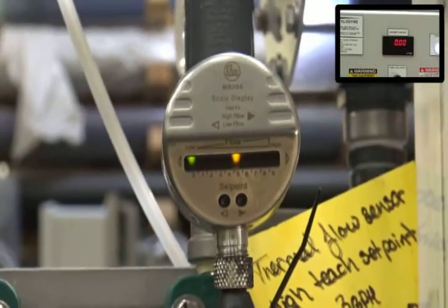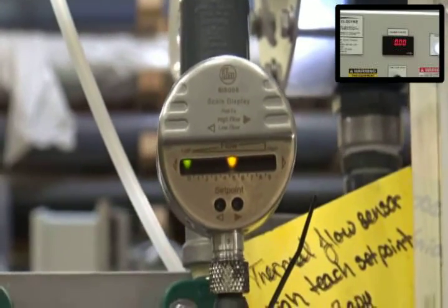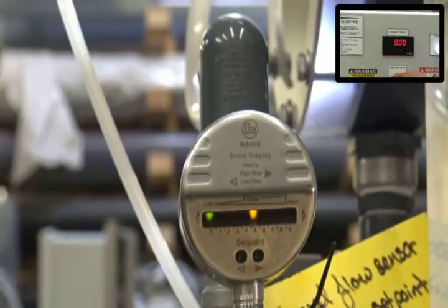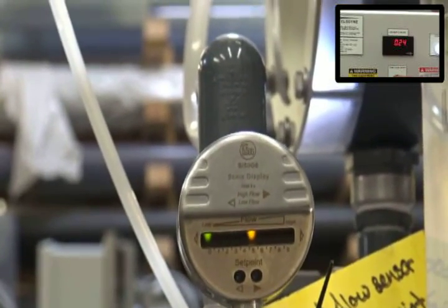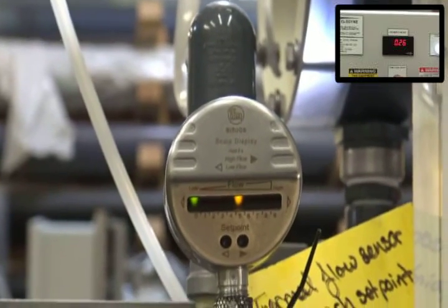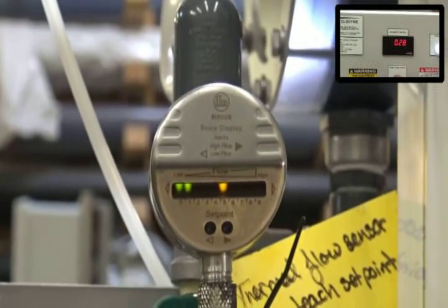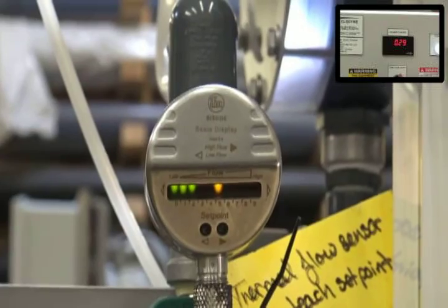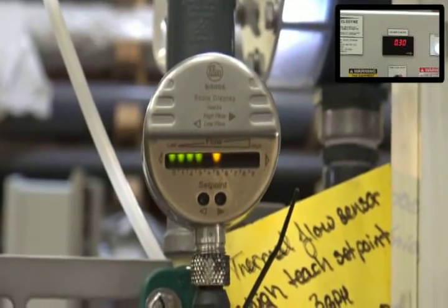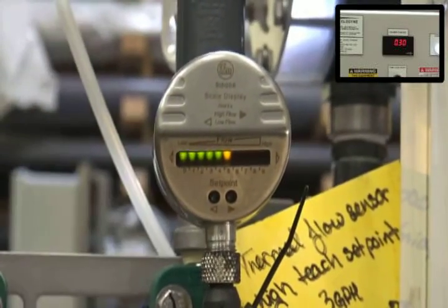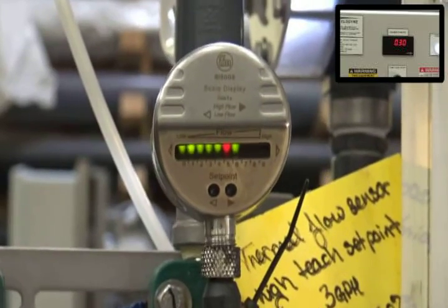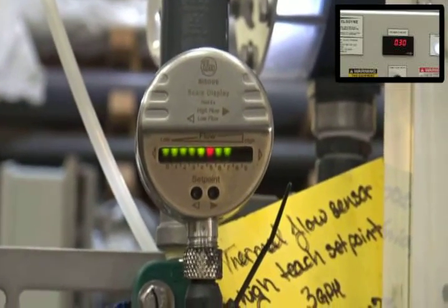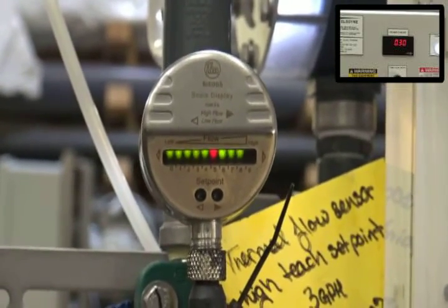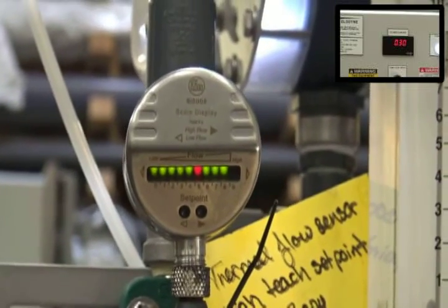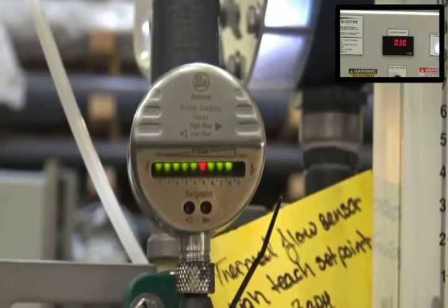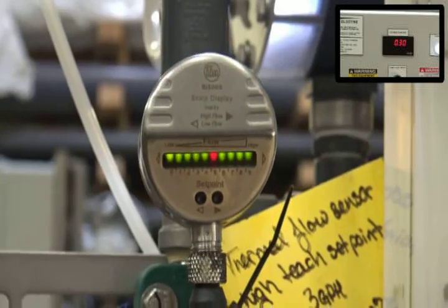Now we will turn it back up to the 0.3, which is where your high teach set point is. And if you notice, those lights will start coming back for us, and then the orange light should turn red. Like that. And we're gonna go ahead and let that run for a second and let it settle out again. And as soon as we're ready, we'll go ahead and do another high teach on this calibration.